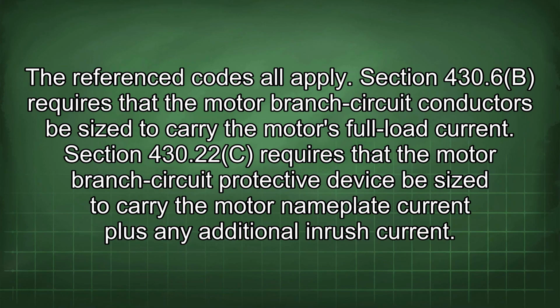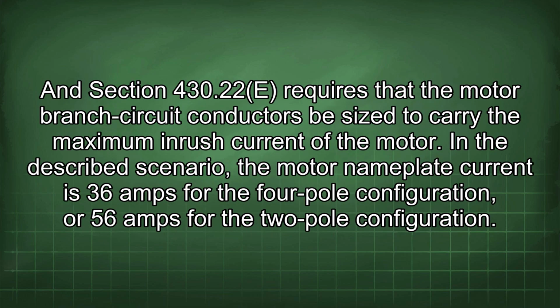The reference codes all apply. Section 430.6b requires that the motor branch circuit conductors be sized to carry the motor's full load current. Section 430.22c requires that the motor branch circuit protective device be sized to carry the motor nameplate current plus any additional inrush current. And Section 430.22e requires that the motor branch circuit conductors be sized to carry the maximum inrush current of the motor.